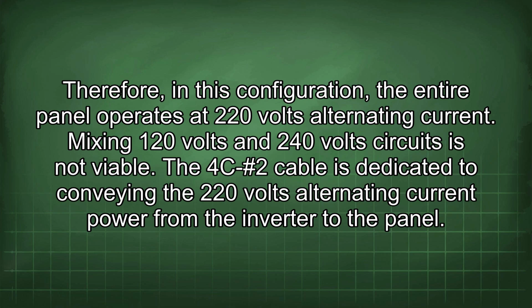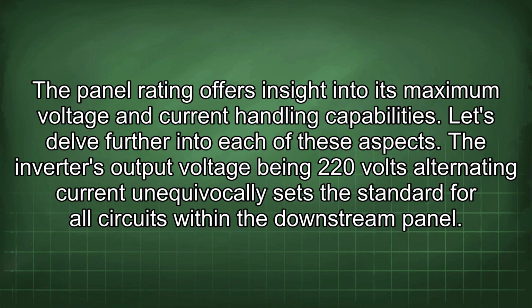Therefore, in this configuration, the entire panel operates at 220 volts alternating current. Mixing 120 volt and 240 volt circuits is not viable. The 4C-2 cable is dedicated to conveying the 220 volts alternating current power from the inverter to the panel. The panel rating offers insight into its maximum voltage and current handling capabilities. Let's delve further into each of these aspects.